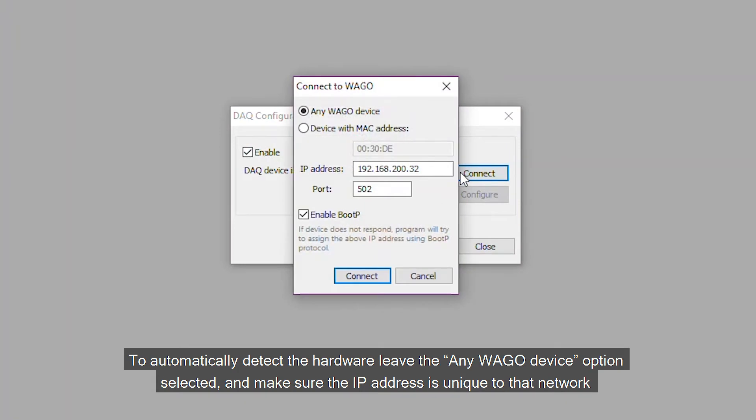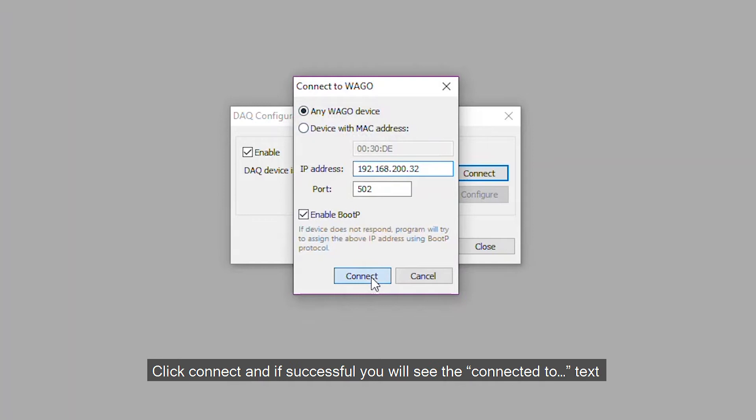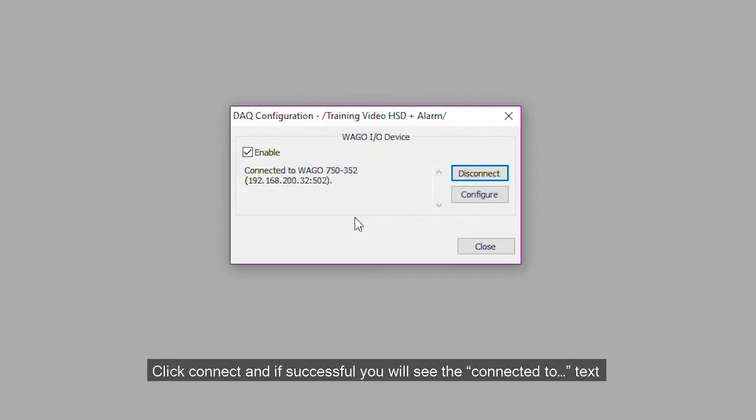To automatically detect the hardware, leave the Any WAGO device option selected, and make sure the IP address is unique to that network. Click Connect, and if successful you'll see the Connected to text.